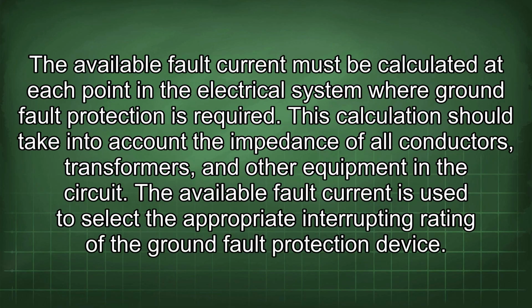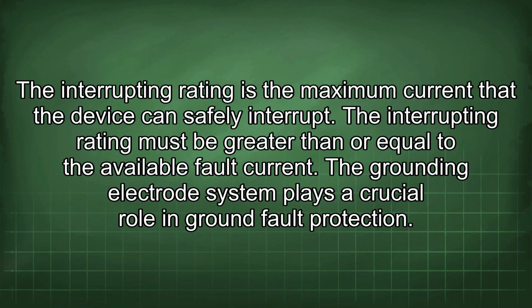The available fault current must be calculated at each point in the electrical system where ground fault protection is required. This calculation should take into account the impedance of all conductors, transformers, and other equipment in the circuit. The available fault current is used to select the appropriate interrupting rating of the ground fault protection device. The interrupting rating is the maximum current that the device can safely interrupt. The interrupting rating must be greater than or equal to the available fault current.